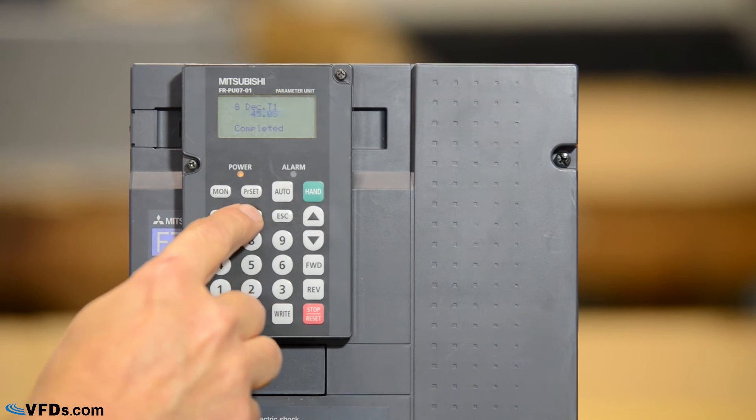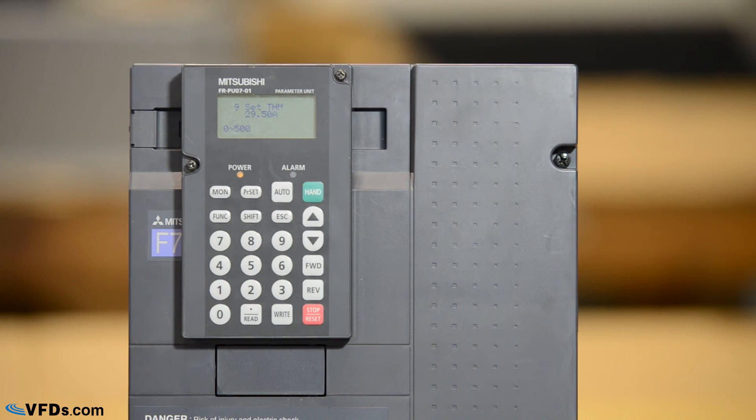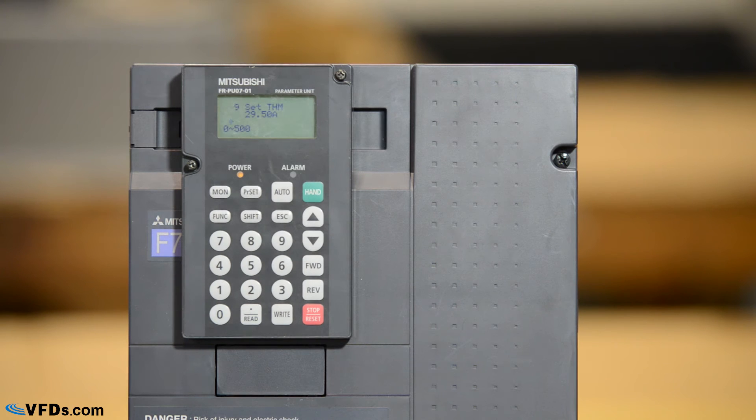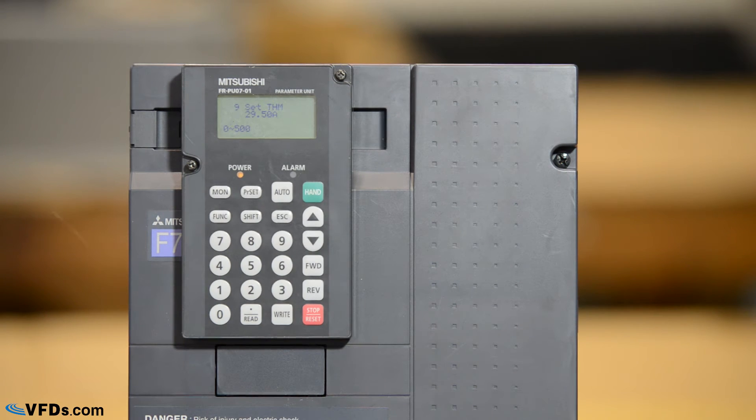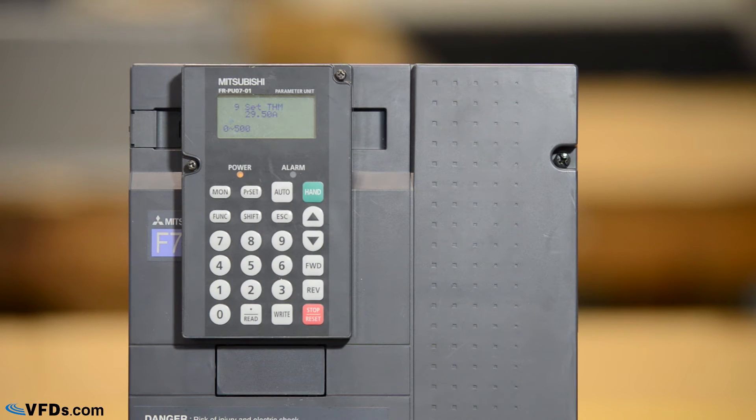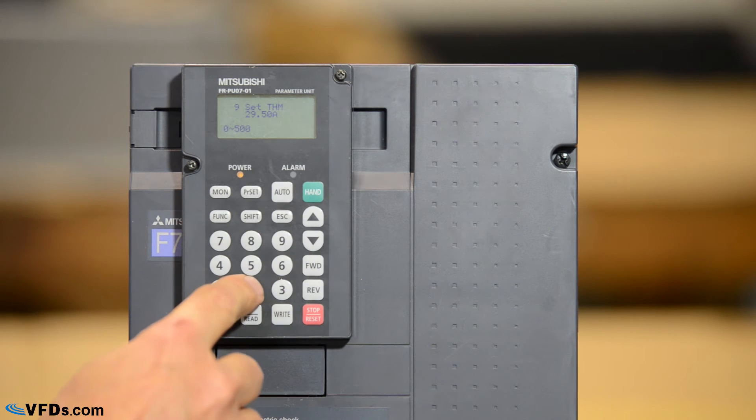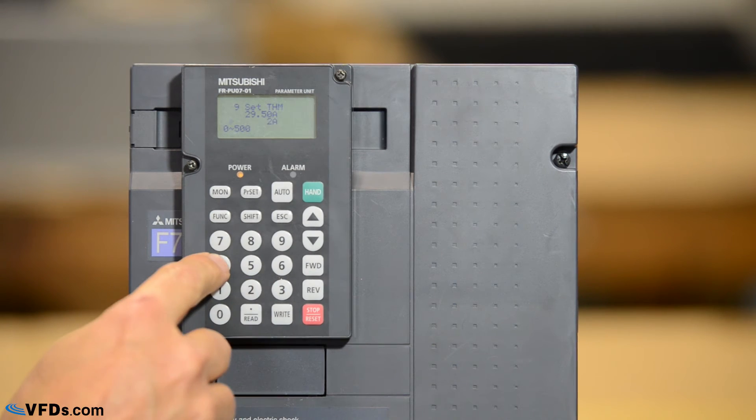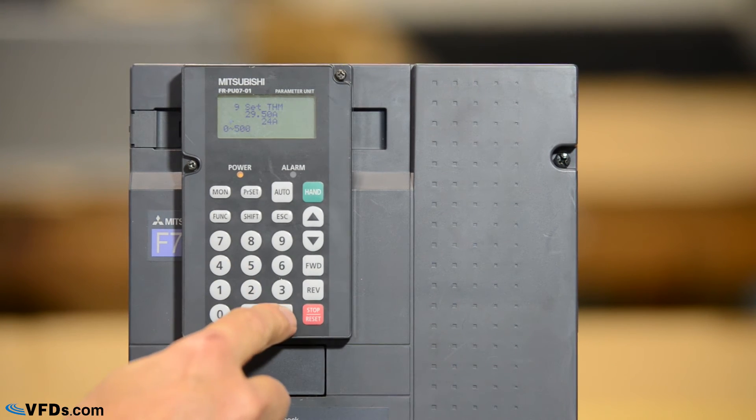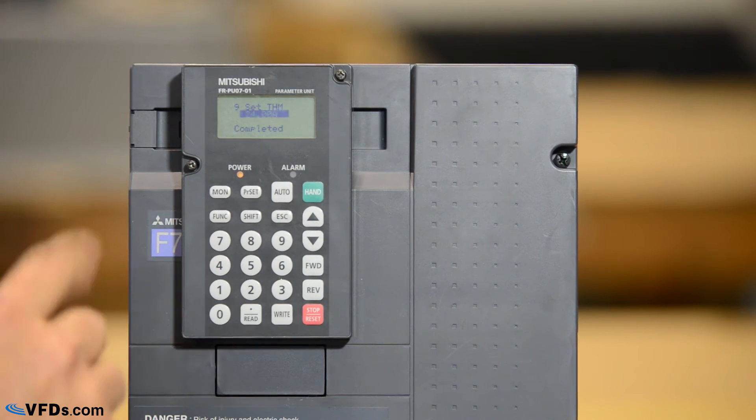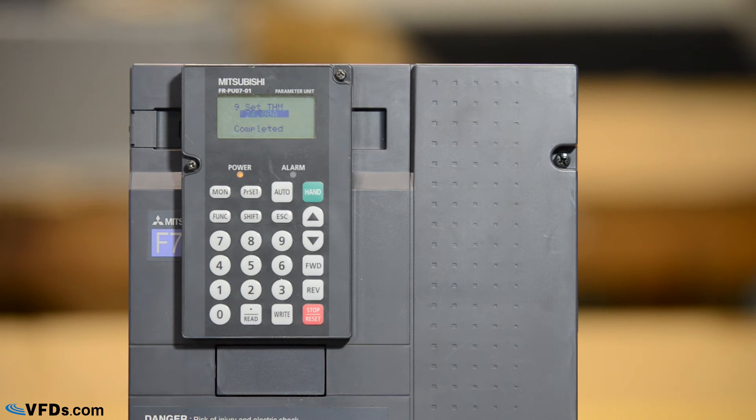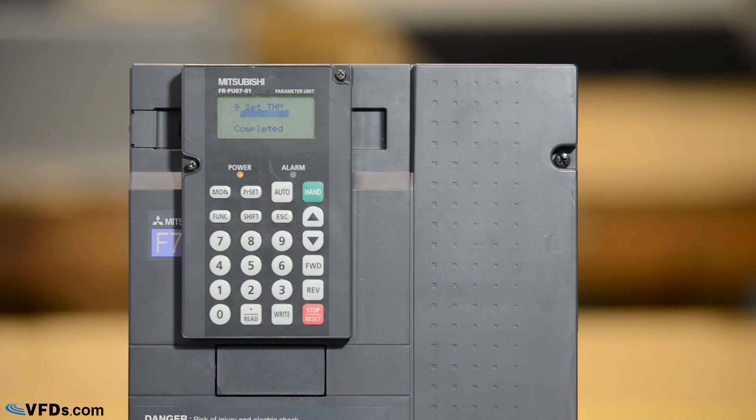And finally we have parameter 9. Parameter 9 is the full load amps of the motor nameplate. My motor nameplate says that it is 24 amps. So I will type 24 and write and this will now protect my motor at its rated current of 24 amps.